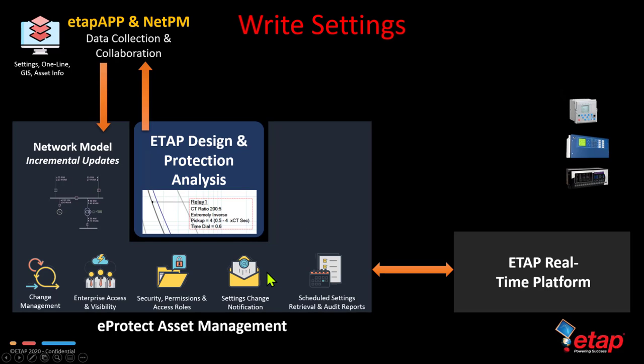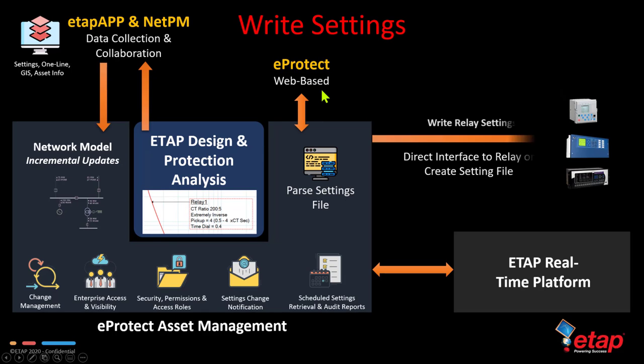And if there is an update on the settings that are arriving from ETAP versus those inside the eProtect database, then a notification is generated again, letting individuals know based on their security and permissions that a change has been updated or added to the eProtect database. The settings are then combined with the rest of the settings from that particular type of relay to create an overall setting file. And then that's visualized inside the eProtect web-based application.